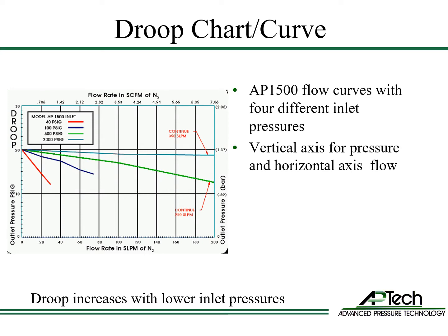You can see the significant impact of inlet pressure on regulator droop. As inlet pressure decreases, droop increases. When sizing a source regulator for gases, it is generally advised to use a flow curve with the intended cylinder change pressure for the inlet pressure. Using an inlet pressure of 200 to 300 psi, for example, as opposed to full cylinder pressure, will allow the user to select the correct regulator.